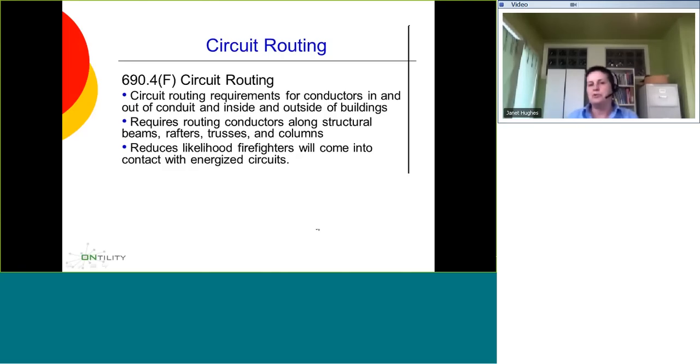It's best to put it where it's over structural members, where it's over rafters or where it's over trusses. If it's inside the building, it needs to be put underneath the structural members. And this is so if a firefighter is coming onto a roof with a fire going on, they can actually vent close to the ridge. They like to vent close to the ridge.